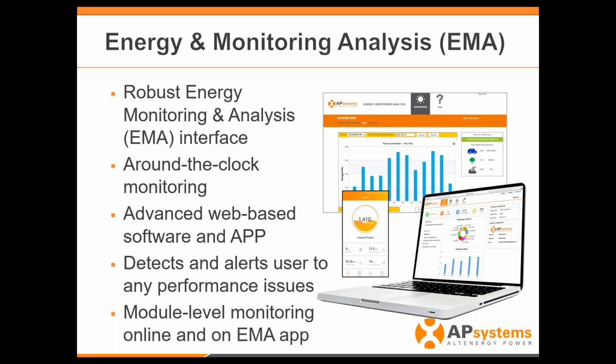The other nice feature we also provide is the alerts. To the installer only, we have the ability to give you alerts for anything on the system that we sense, based on the algorithms, is an issue. In the past, we alerted you of everything and ended up creating spam and sending you too much information. So we've backed off on that. We only alert you of the things that are actually critical. And the most important part is it has to persist for 3 days before we notify you.